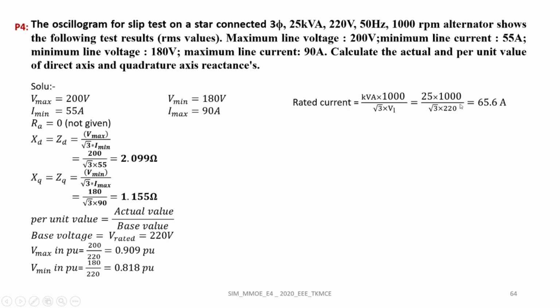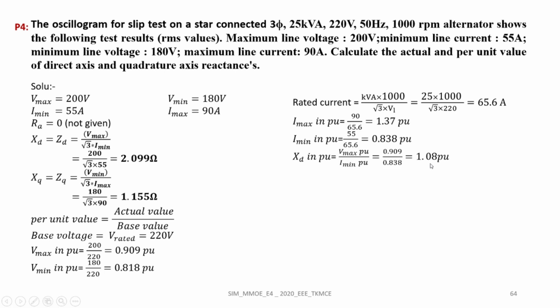So rated current is obtained as 65.6 ampere. Now we need to convert I min and I maximum into per unit. Now I max in per unit is 90 by 65.6, that is 1.37 per unit. I min in per unit is obtained as 0.838 per unit. Now we can compute XD. XD is equal to Vmax in per unit by I min in per unit, that is obtained as 1.08 per unit. Similarly, XQ in per unit is equal to Vmin in per unit by Imax in per unit, which is obtained as 0.597 per unit.